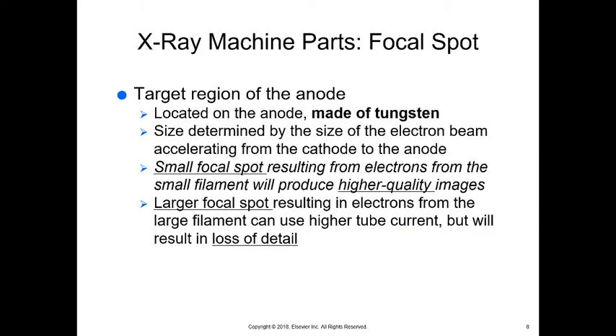Now we have a focal spot — the targeting area on the anode, also made of tungsten. The size of the focal spot is determined by the size of the electron beam accelerating from the cathode. A small focal spot from the small filament produces higher quality images. A large focal spot from the large filament can use higher tube current but results in loss of detail.